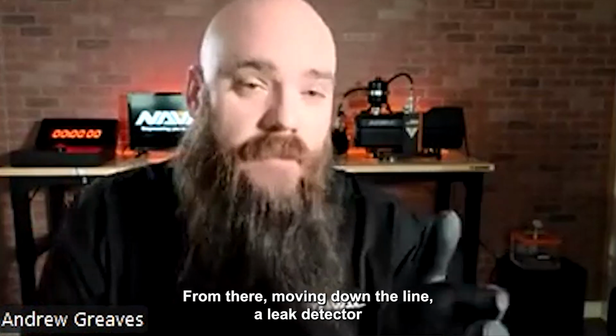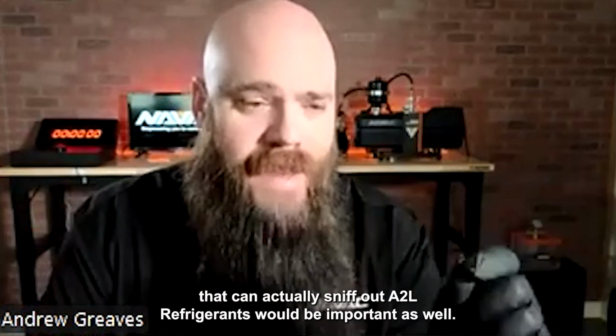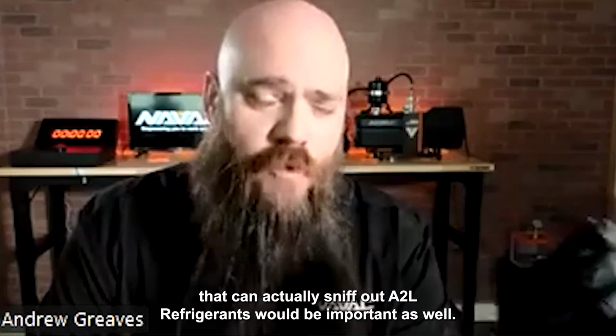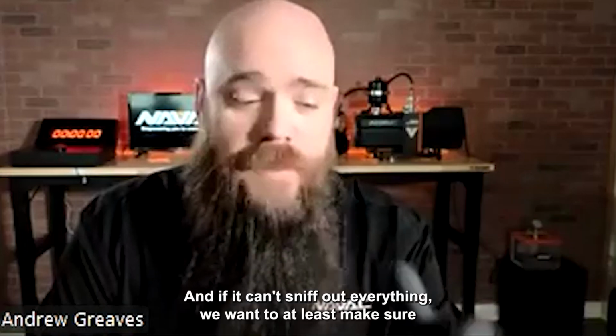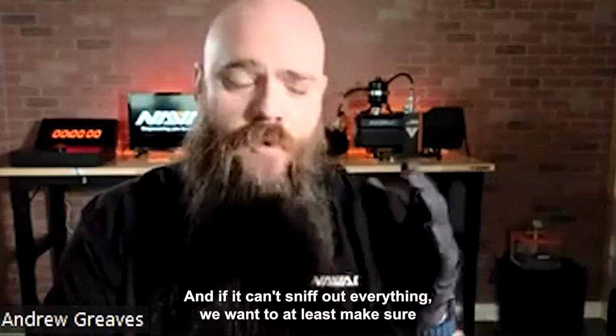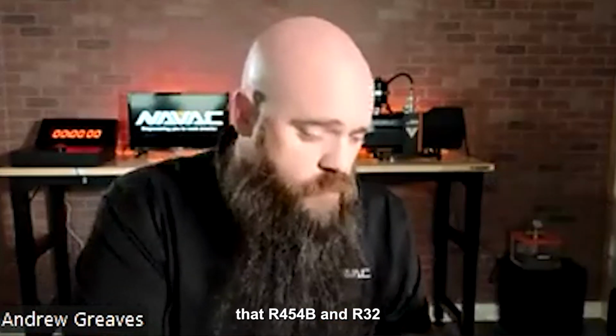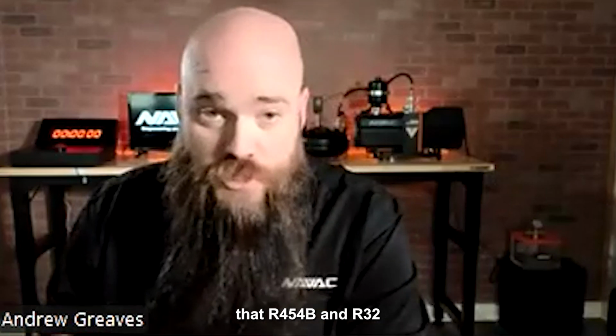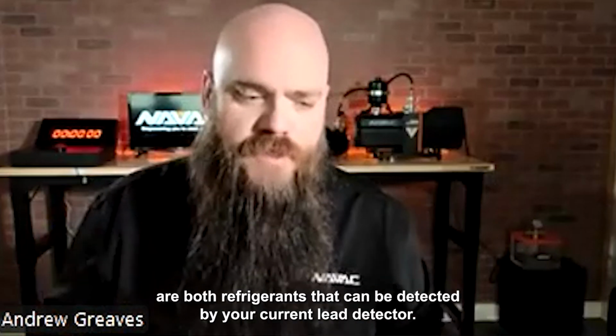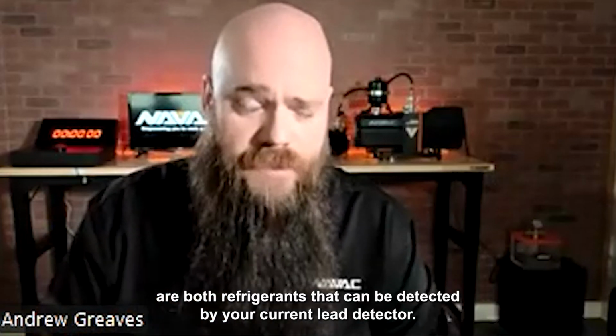From there, a leak detector that can actually sniff out A2L refrigerants would be important as well. And if it can't sniff out everything, we want to at least make sure that R454B and R32 are both refrigerants that can be detected by your current leak detector.